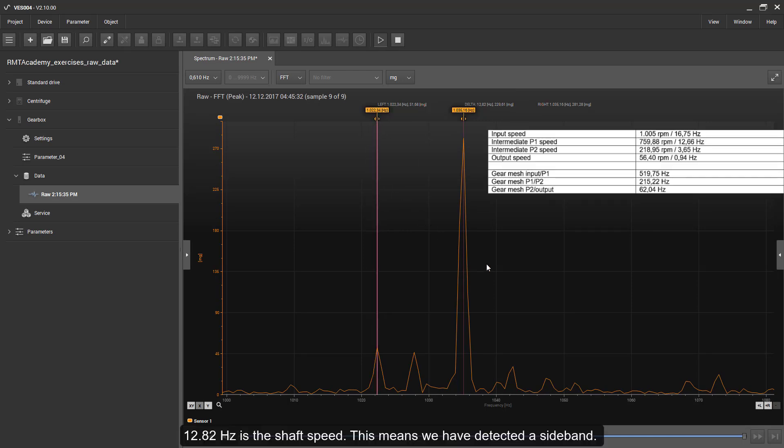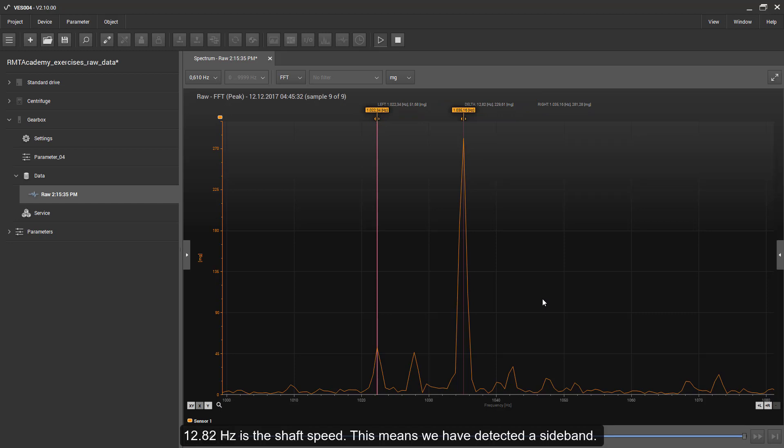12.82 Hz is a shaft speed, this means we have discovered a sideband.